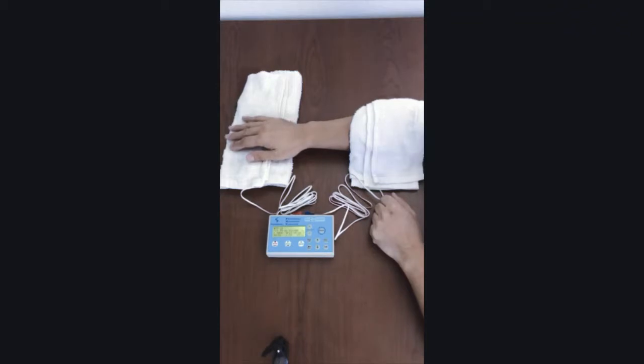If you see either channel 1 or channel 2 lights flashing, that means you are not getting enough microcurrent, or you may not be getting any microcurrent at all. You need to figure out what may be wrong. The problem may be that the skin is too dry, there is a weak or bad electrode, or a bad wire.